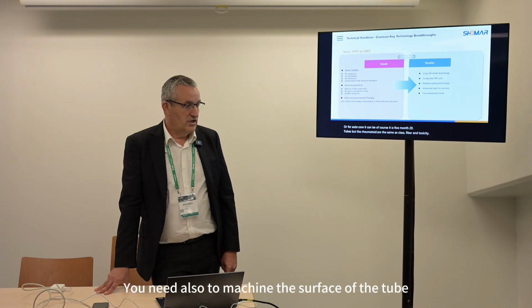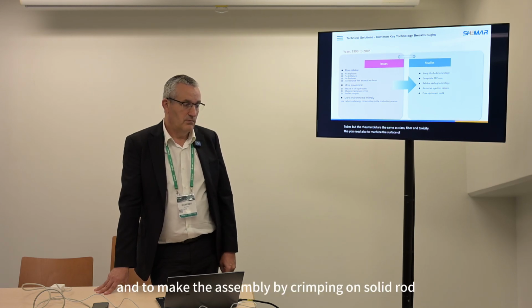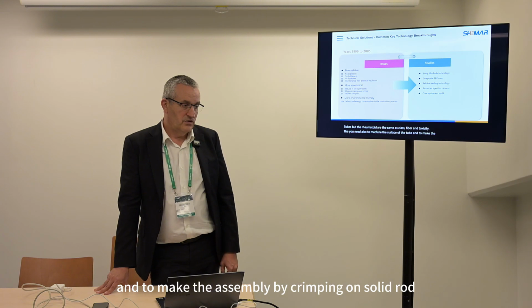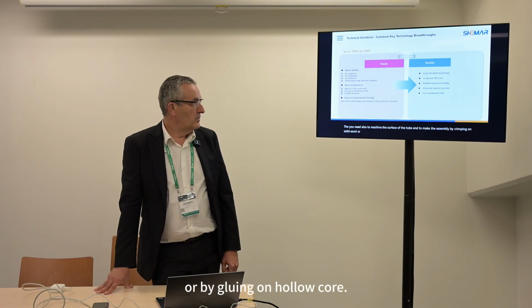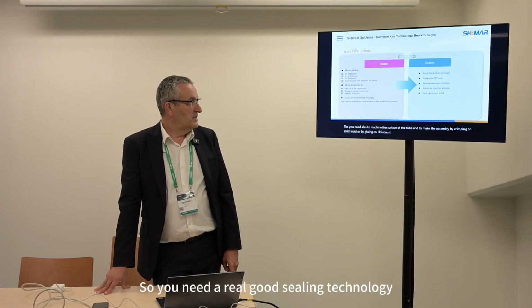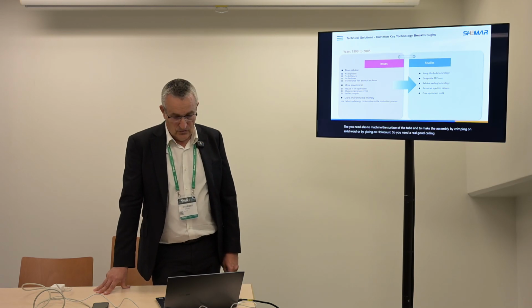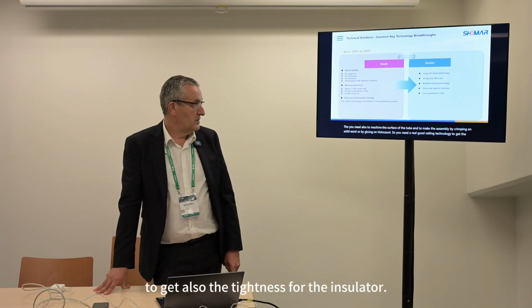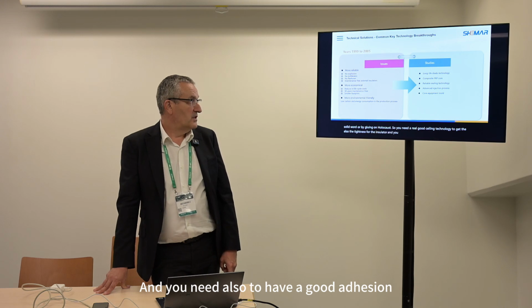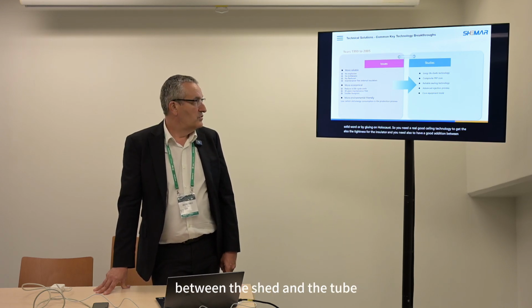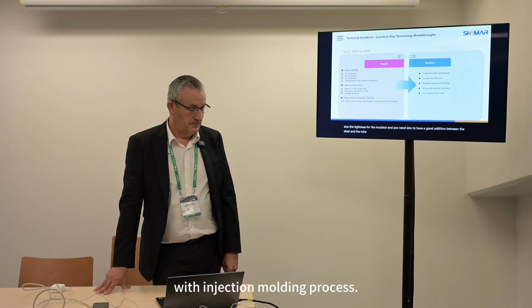You also need to machine the surface of the tube and make the assembly by crimping on solid rod or by gluing on hollow core. So you need a really good sealing technology to get the tightness for the insulator. And you also need a good adhesion between the shed and the tube with the injection molding process.